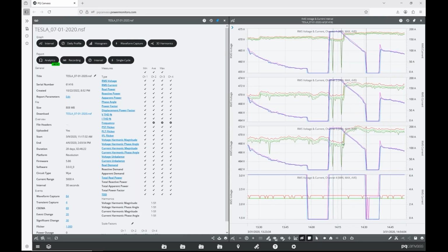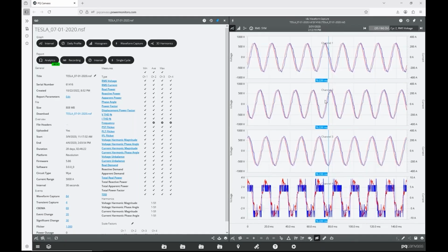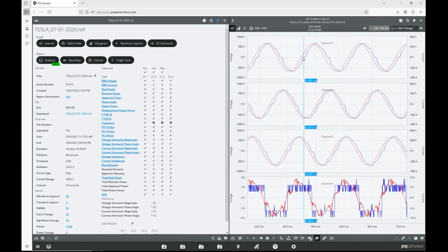We can look at the waveform for one of these sags to confirm that indeed the current didn't really change at all. And you can see that at high currents, it's a nearly perfect waveform. The power factor is very good. You see some crossover distortion, zero in the current. But overall, it's a fairly low distortion current waveform.